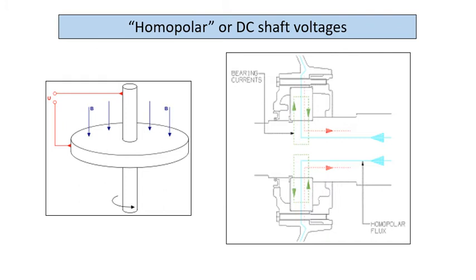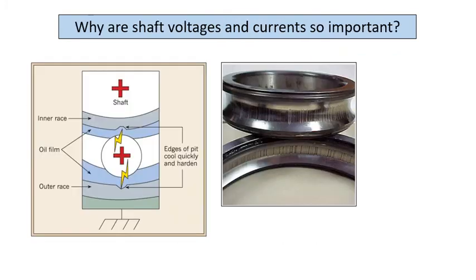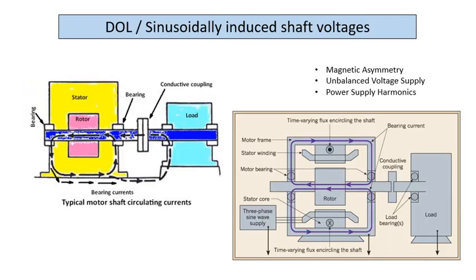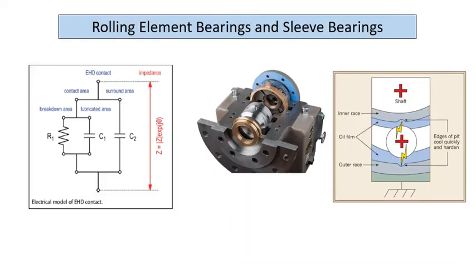You need a lower shaft voltage to cause damage. Sleeve bearings can tolerate more. And even the difference between a cylindrical roller bearing versus a ball, because you've got a narrow, smaller contact point. So your oil film will be thinner. I've already discussed this. Also, just there, power supply harmonics, another cause of shaft voltages. Otherwise, the rest is pretty much a repeat of everything before.